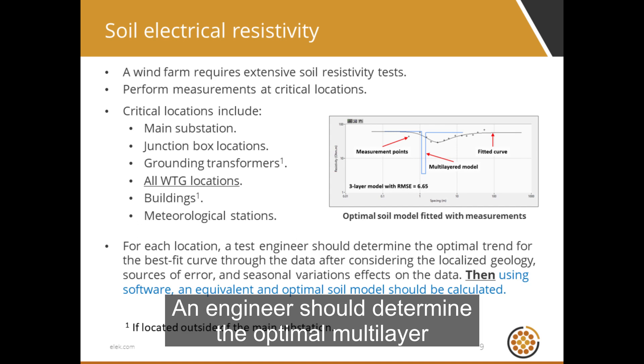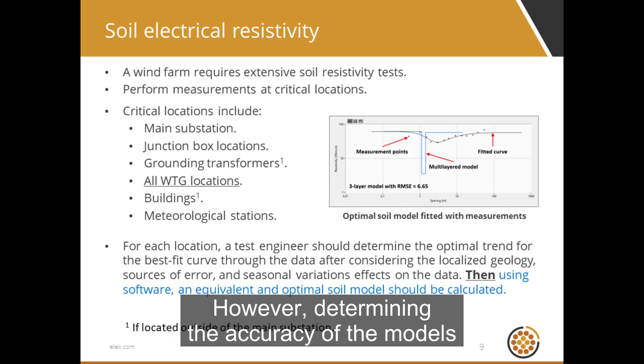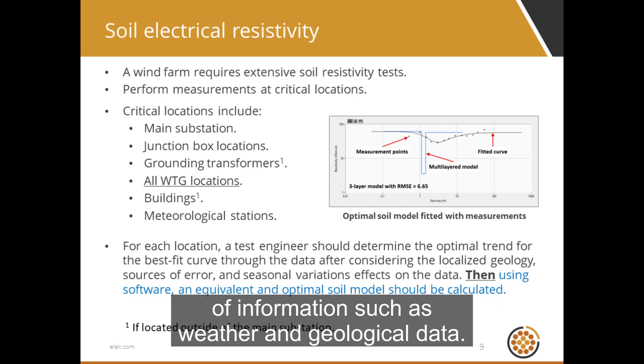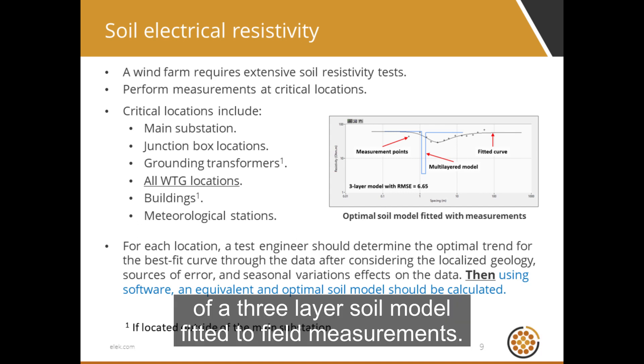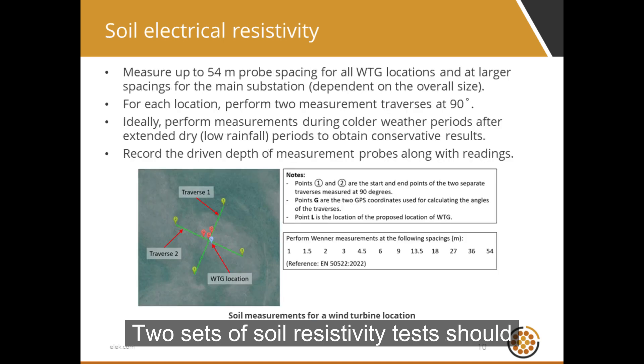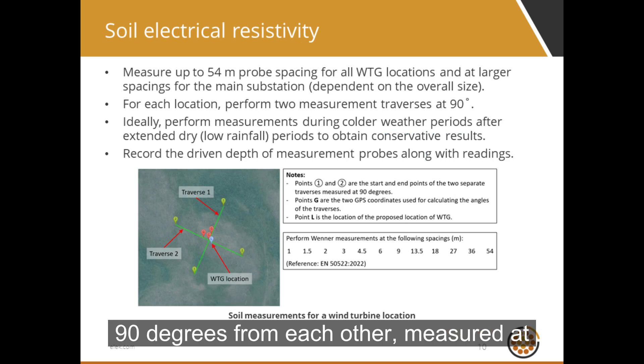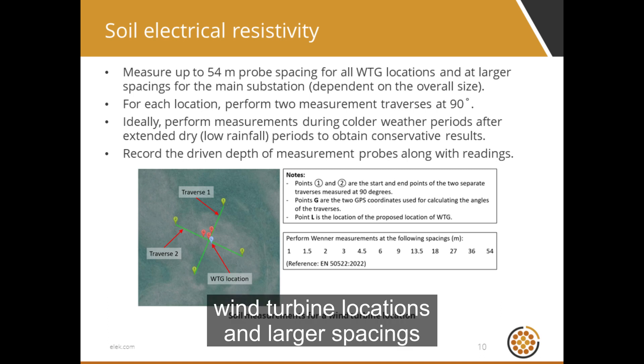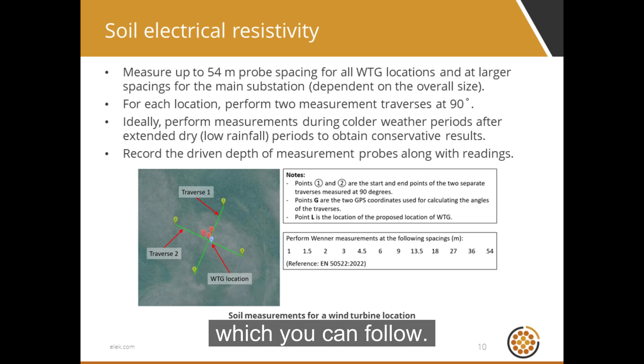An engineer should determine the optimal multilayer soil model for each critical location using software modeling. However, determining the accuracy of the models involves engineering judgment considering other relevant sources of information such as weather and geological data. The image here shows a computer simulation of a three-layer soil model fitted to field measurements. Two sets of soil resistivity tests should be undertaken at each critical location at 90 degrees from each other. Measure at probe spacings up to 54 meters for all wind turbine locations and larger spacings for the main substation. The British Standard provides recommended probe spacings which you can follow.